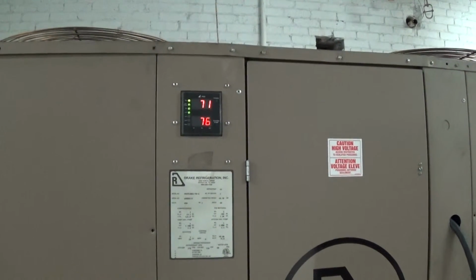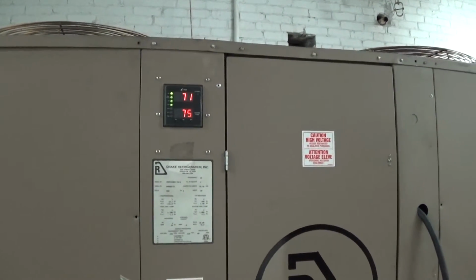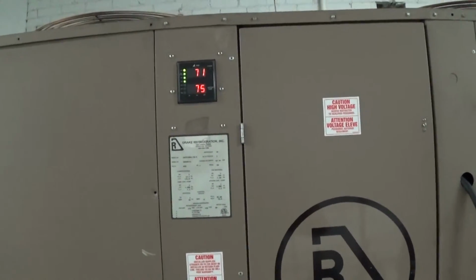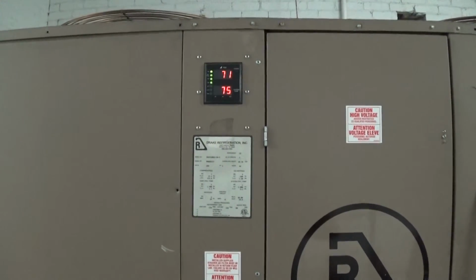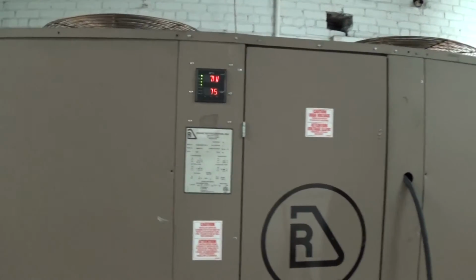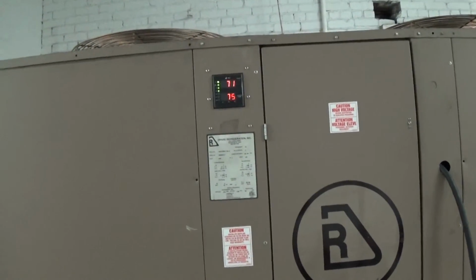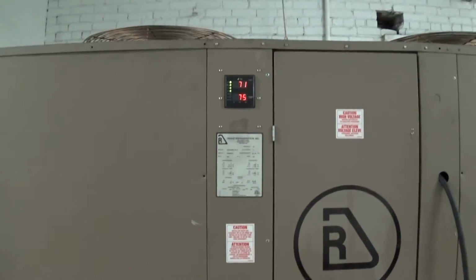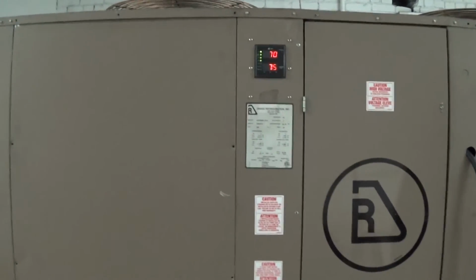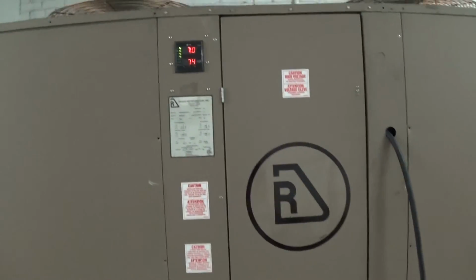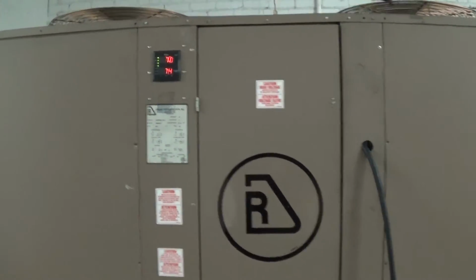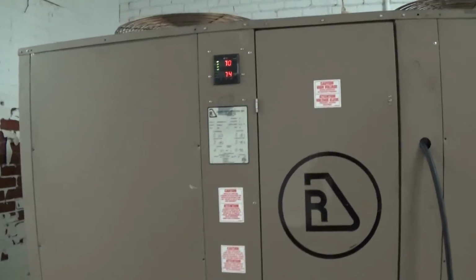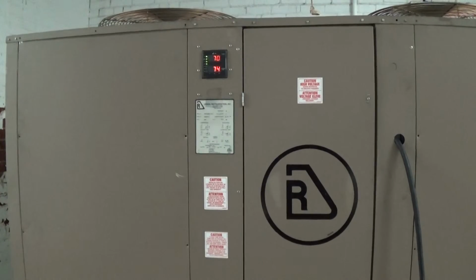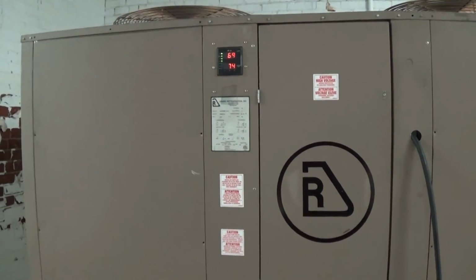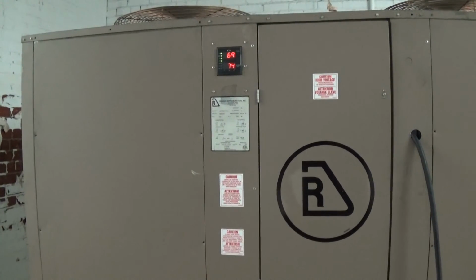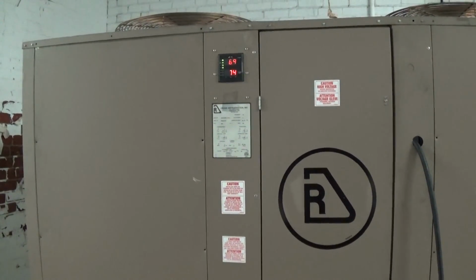So we get 50 and 52 respectively, so we can hear the two compressors go off. You probably don't want to have both compressors at the exact same settings, because then you won't take advantage of some of the staging. If, say for example, you have both of them set at 50, and you have one at a differential of 2 and one at a differential of 4, then one compressor will handle the load if it can do it. If it can't, it's going to creep above that 2-degree differential till it hits the 4-degree differential, for example, then kick in your second compressor. And you want to have some differences there just to take advantage of the dual compressor circuit.